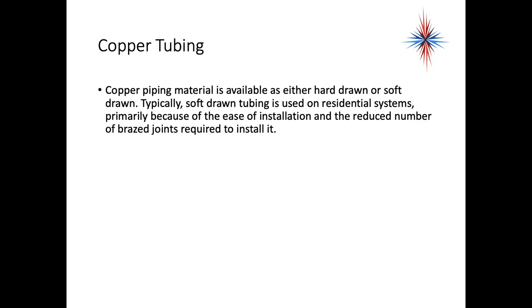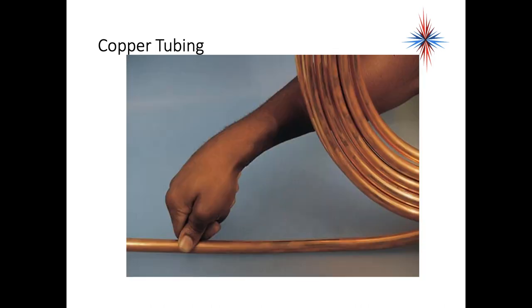Copper piping material is available as either hard drawn or soft drawn. Typically, soft drawn tubing is used on most residential systems, primarily because of the ease of installation and the reduced number of brazed or soldered joints required. Remember, every time you put a joint in, every time you put a fitting in, you have a chance for a leak. This is an example of copper tubing—this is how you can actually bend out copper tubing.